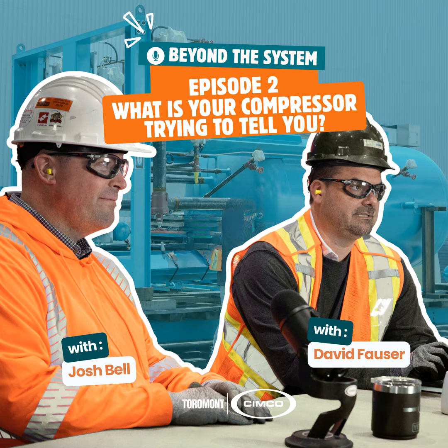Motors typically require grease for the bearings. You're going to want to record when that's happening. One very critical thing for greasing bearings: make sure you stay consistent with the type of grease you use. You don't want to be putting a variety of grease. If you have a grease gun with a tube of grease in it from your Zamboni, it may not be the right application for your motor. Make sure you have dedicated tools, make sure the area is clean, and make sure you record all of that information.